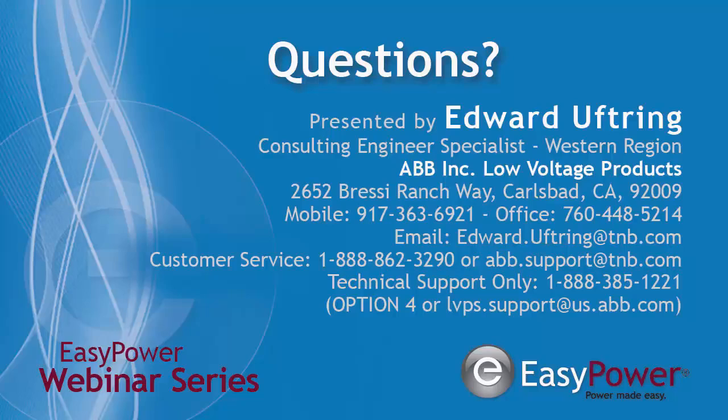Accounting for X/R ratio, can a breaker be returned to service after? Yes, it absolutely can. We have our own services, and a lot of our partners in the business also have services. Our services can reset it, even if it's interrupted at its full rating. We can do services on the contacts. We're unique in that ABB can do services as far as the arc chutes as well. So after your arc chutes, you want clean arc chutes, we are able to go out there and clean them. Basically, our service guys almost make it brand new.